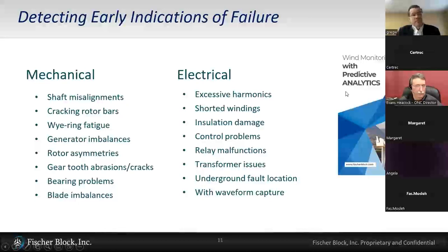And interestingly, although we're looking at electrical signals, we're able to ascertain the health of many of the mechanical components as well as the electrical system components. And we've got some slides later on in this presentation that show some case studies whereby we monitor the electrical signals either emanating from the generator or being consumed by the motors, the rotating equipment. The sine waves are not perfect. They have distortions that are very consistent, and they can be associated with, as you can see here, gear problems, bearing issues, winding problems, transformer issues, relay integrity, and so forth. So this platform of electrical signature analysis provides early indications of both mechanical and electrical issues within a plant.